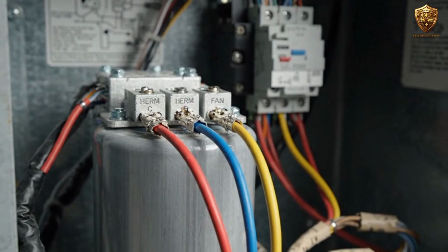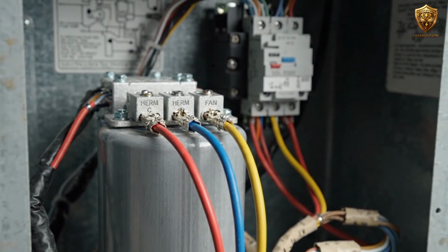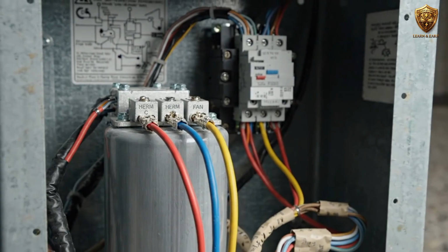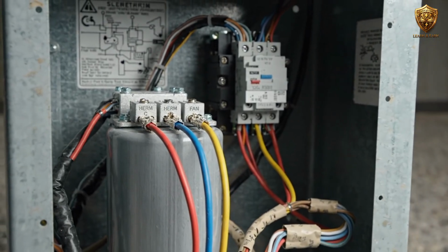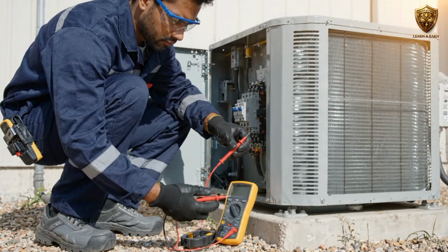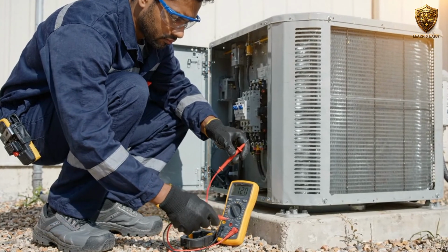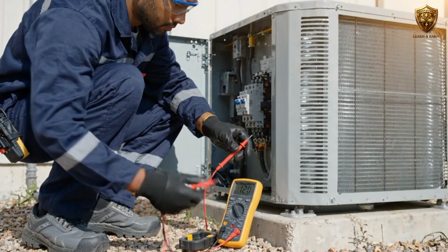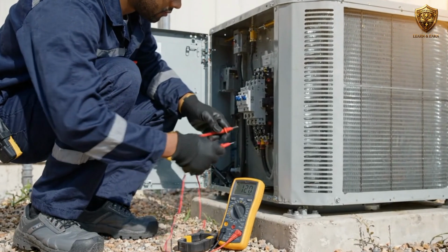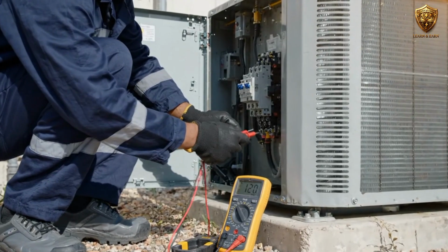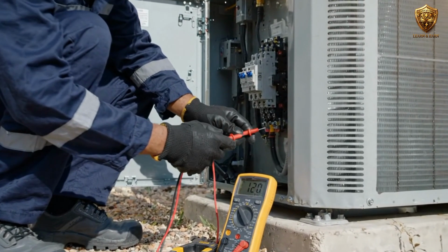If the system has no incoming power, replacing a capacitor will not solve the problem. If the contactor is not receiving the correct control signal, the compressor and condenser fan may never receive line power. If the contactor is energized but the motors do not operate correctly, then the investigation moves further into the high-voltage circuit.